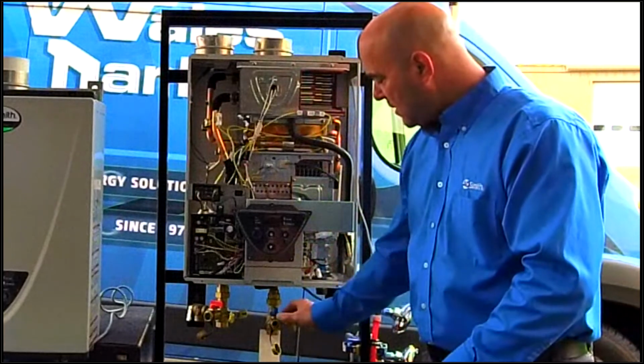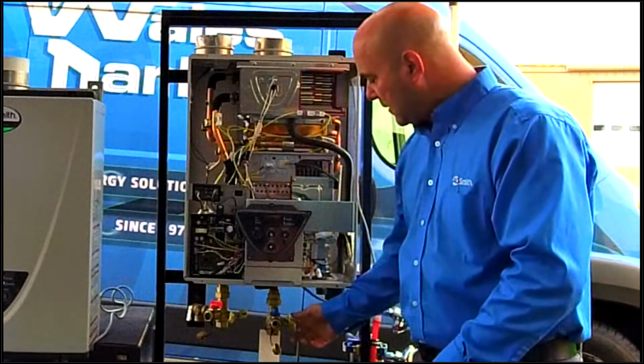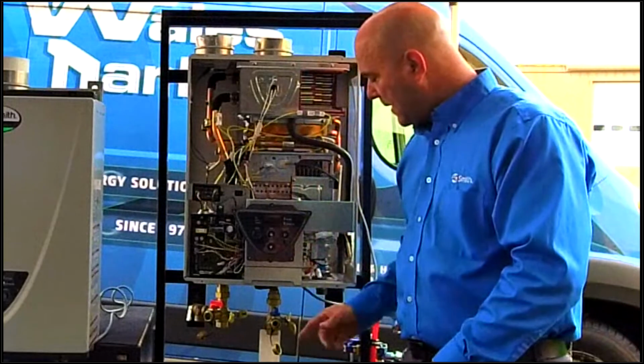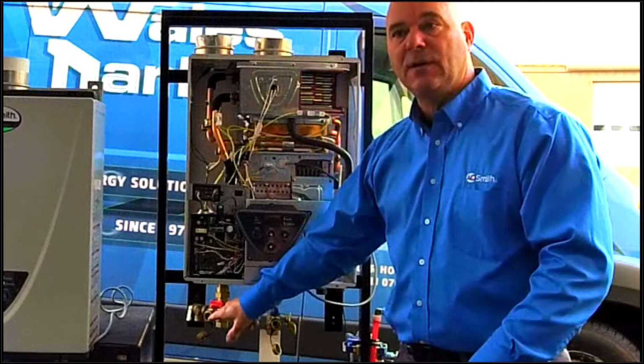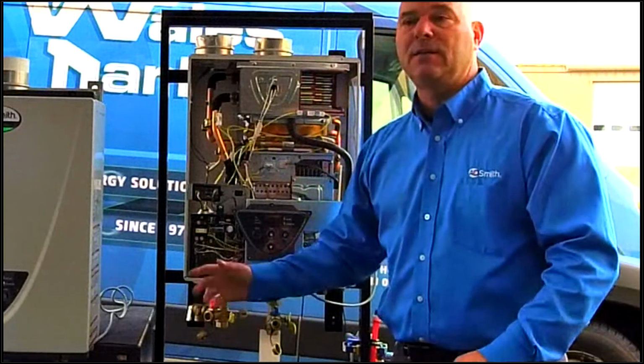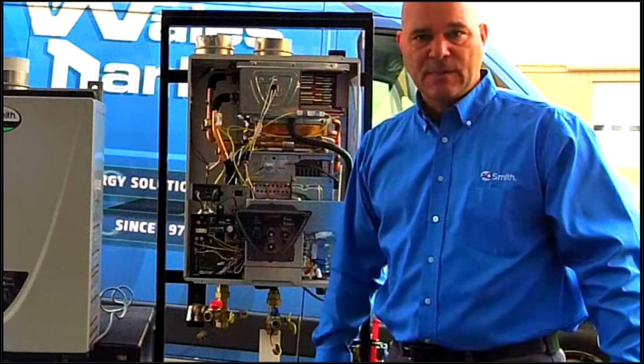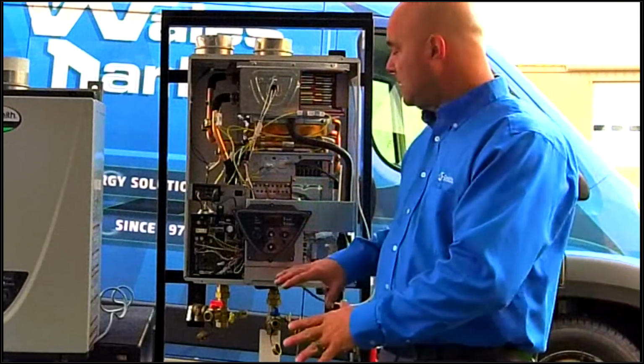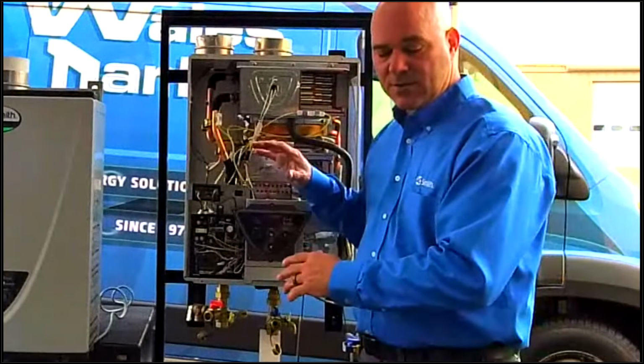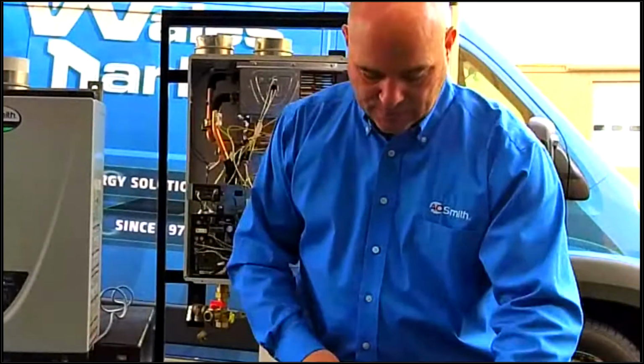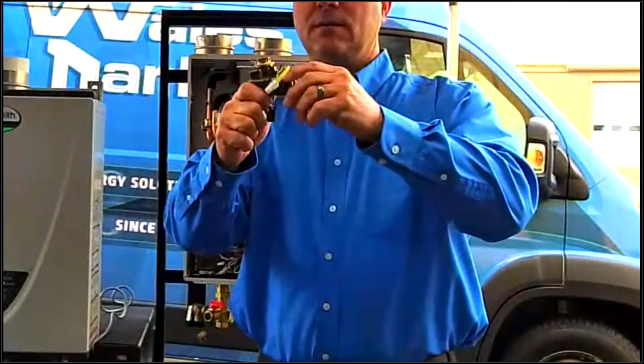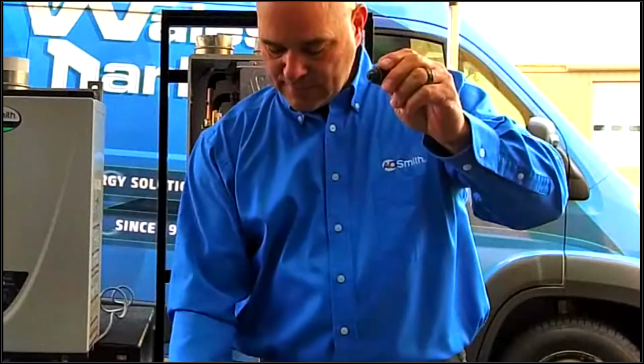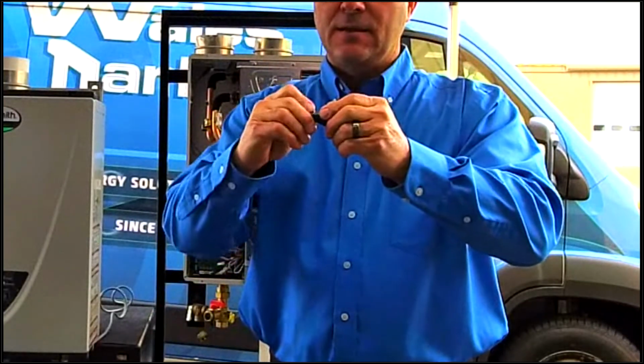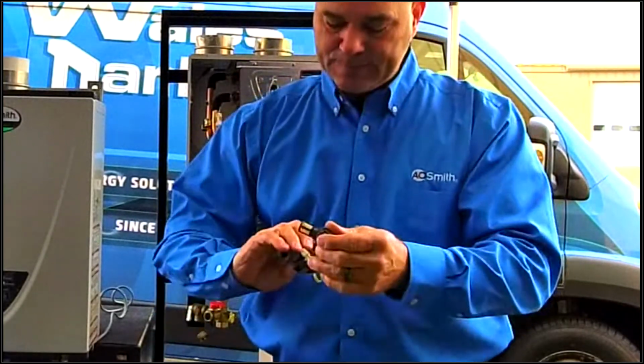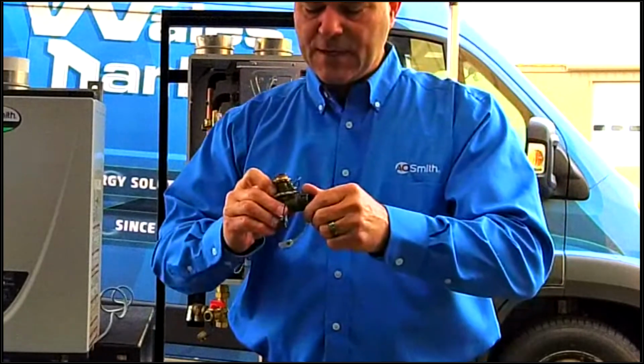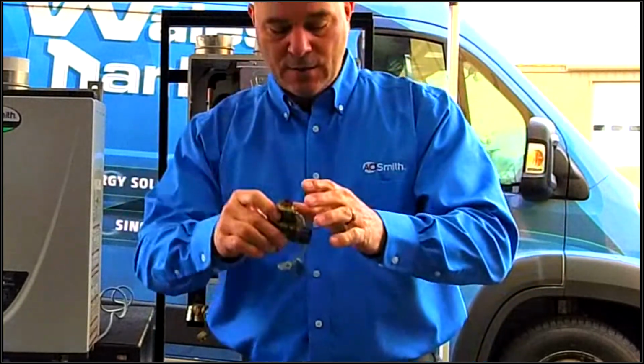You're going to take your hoses off. You're going to close these valves. You're going to open your cold water main, and you're going to flush everything out of your hot water into that bucket. And you may do that once or twice. After you're done flushing the heat exchanger, you've cleaned the heat exchanger, you've flushed it. You're going to take your cold water inlet. You're going to pull the little black cap out. You're going to pop your screen back in place. You're going to put it in there, and away you'll go.